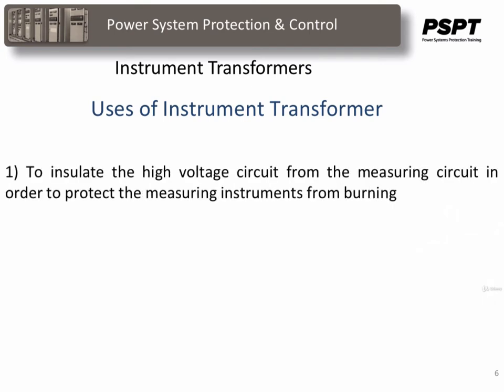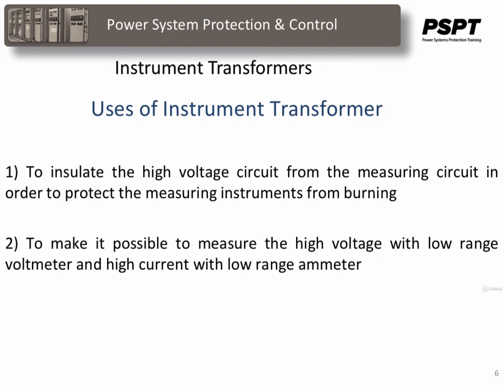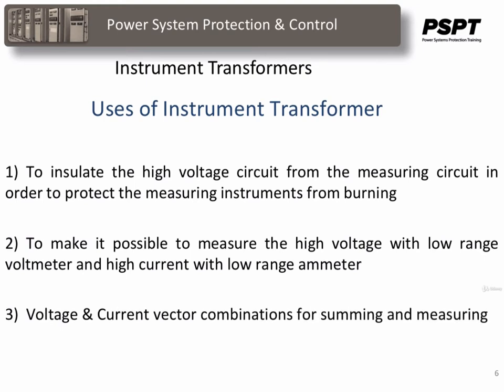Instrument transformers are used for the following reasons. 1, to insulate high voltage circuits from the measuring circuit in order to protect the measuring instrument from damage. 2, to make it possible to measure high voltage with low range voltmeters and high current with low range ammeters. These instrument transformers are also used in controlling and protecting circuits to operate relays, circuit breakers, etc. Voltage and current phasors can be summed easily on the secondary circuits of these transformers without causing short circuits, as would happen if you were trying to, say, sum 2 currents on the primary side. So a lot of times when you want to sum various currents, say, in a circuit and measure them, you can do this quite safely on the secondaries of current transformers.